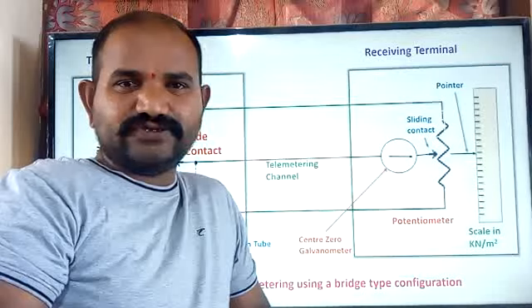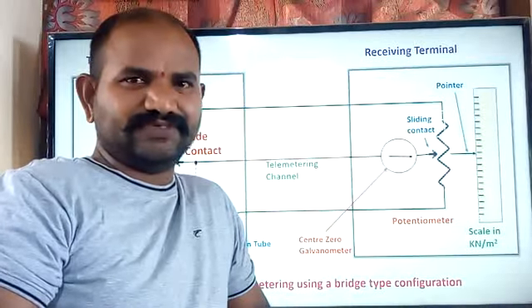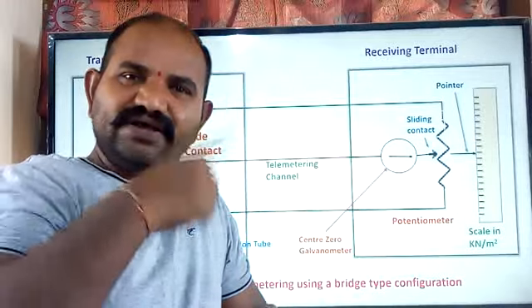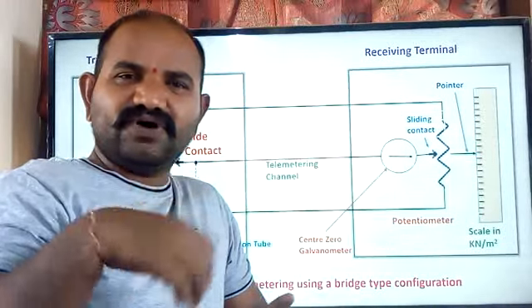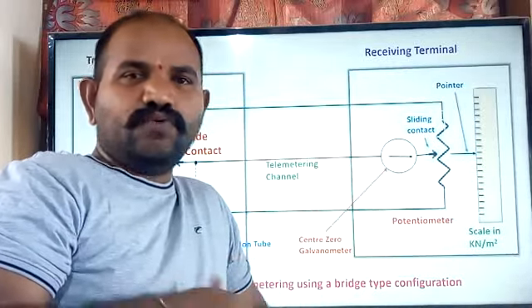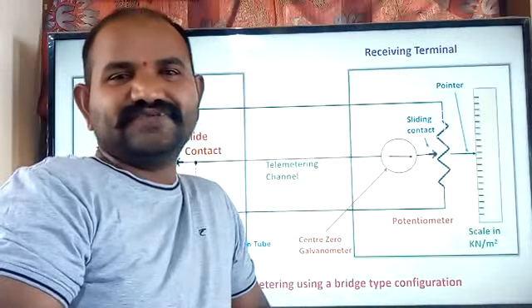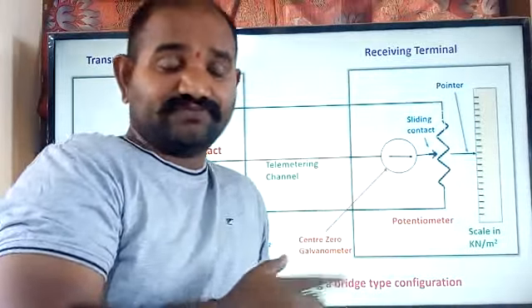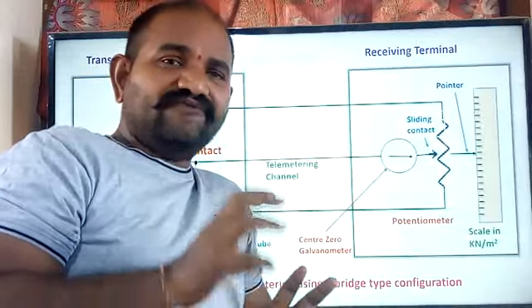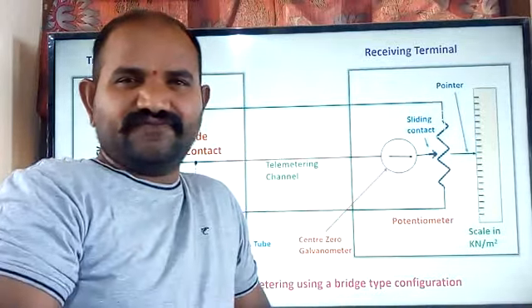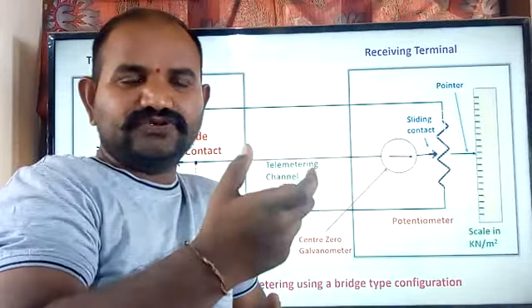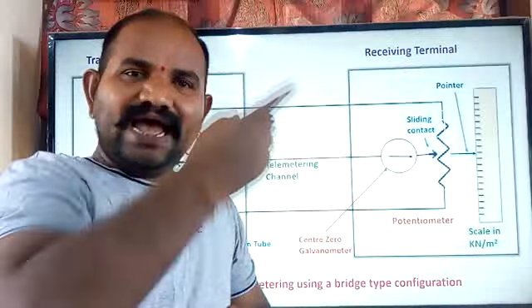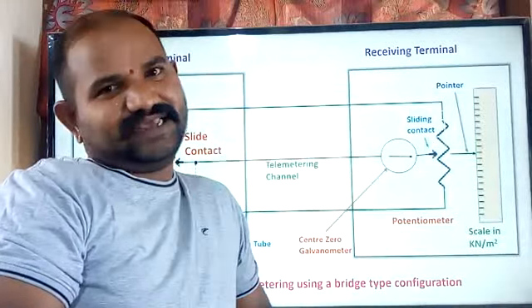One arm acts as a transducer — similar to how we placed a temperature sensor in one arm of the Wheatstone bridge and adjusted the applied voltage for balanced condition. Once the bridge is balanced, it is ready to measure variations in the physical quantities of interest. When there is a change in a physical parameter like temperature or pressure, the transducer resistance changes, the bridge becomes unbalanced, and that unbalanced value becomes our reading.